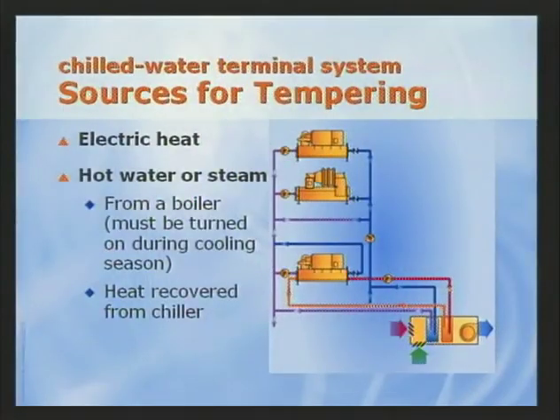In a chilled water terminal system, the heat used for supply air tempering is typically provided by electric heat or a hot water or steam coil. Now, if the system contains a boiler, it needs to be available to operate during the cooling season to provide this type of humidity control. And the school's personnel responsible for the HVAC system need to be made aware of this. As an alternative, using heat that is recovered from the chiller may allow the boiler to be shut down during the cooling season and can also reduce system operating costs by avoiding the use of new energy for reheat. Furthermore, heat recovery may allow the system to meet requirements of local codes and energy standards such as ASHRAE's 90.1.